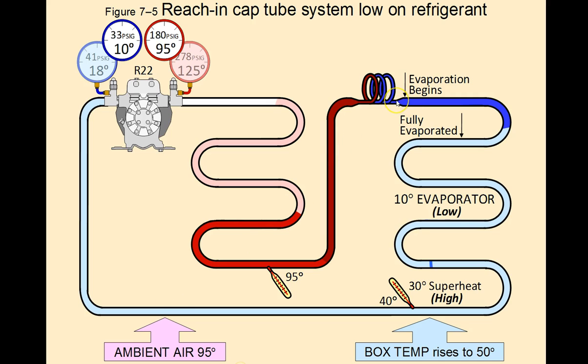So one more time: we leave the cap tube, evaporation begins, and the refrigerant evaporates very early on in the evaporator coil. The refrigerant is fully evaporated and has changed state completely. Only the first portion of the coil provides usable refrigeration. Then we begin to pick up superheat very early — it goes from 10 degrees to 20, to 30, to 40 degrees of temperature — ending up with 30 degrees Fahrenheit of superheat. Because there's not enough refrigerant to maintain box temperature, the box temperature rises to 50 degrees and won't go any lower no matter what. The customer is telling you the thermostat is set as low as it'll go, and the box temperature won't get below 50 degrees Fahrenheit.